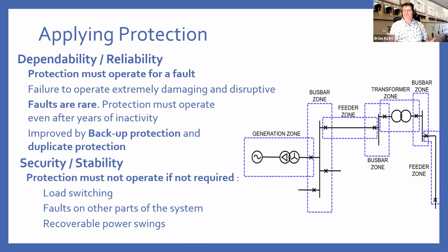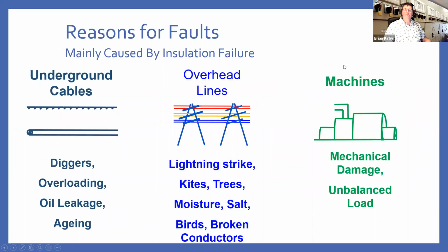But at the same time, if you've got something happening on your network that is abnormal but is not a fault, you don't want your system to trip, because what you don't want to do is to turn a stable power swing, for example, into an unstable power swing by losing part of your generation. So if you've got load switches and faults elsewhere on the network, you need to maintain your supply as much as possible.